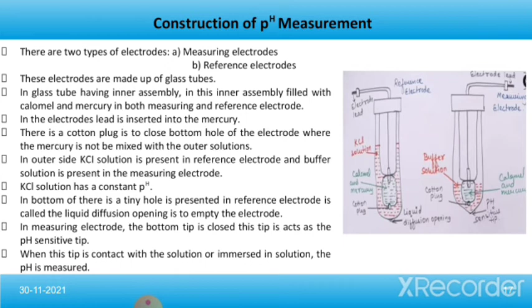Now, KCl solution has a constant pH. At the bottom of the reference electrode there is a tiny hole, which is called the liquid junction diffusion opening, which is used to empty the electrode. In the measuring electrode, the bottom tip is closed. This tip acts as the pH sensitive tip. When this tip is in contact with the solution or immersed in the solution, the pH is measured here in the case of the measuring electrode.